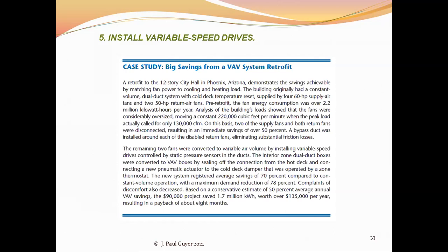Complaints of discomfort from occupants also decreased, and based on a conservative estimate of 50% average annual VAV savings, the $90,000 project saved 1.7 million kilowatt hours of energy with a value at the time of about $135,000 per year. So that was a payback period of about 8 months.